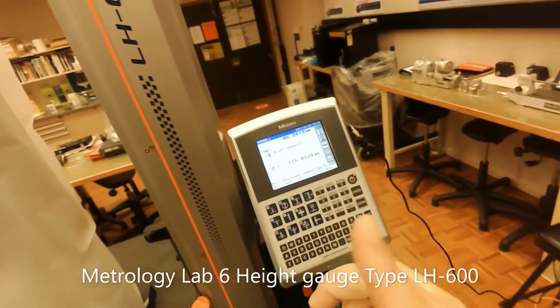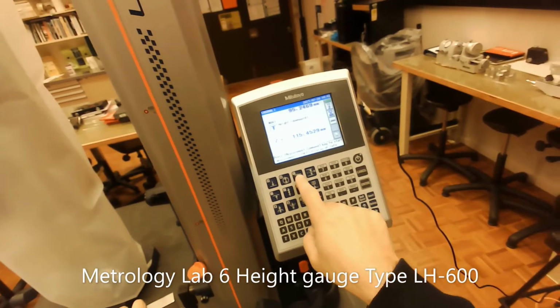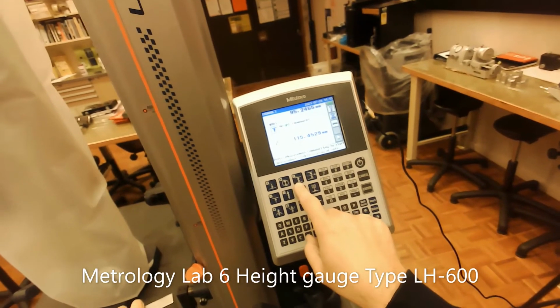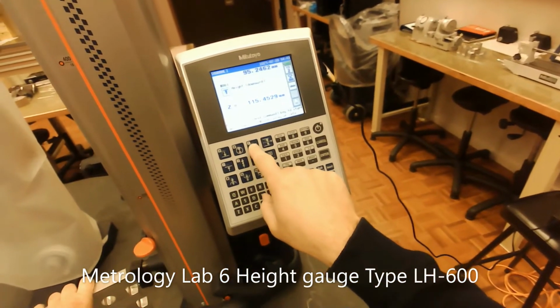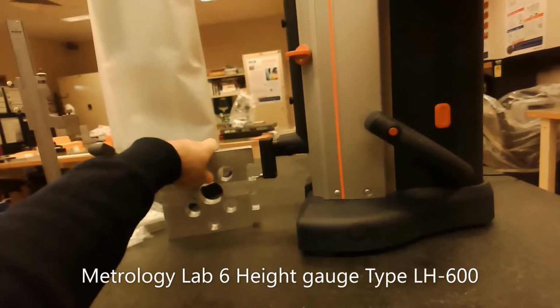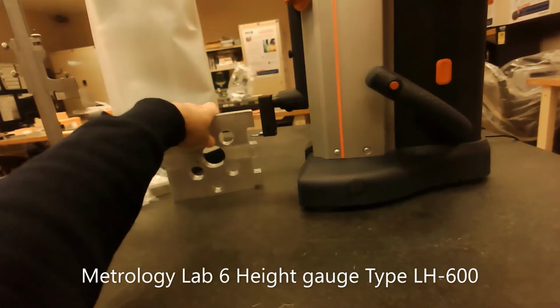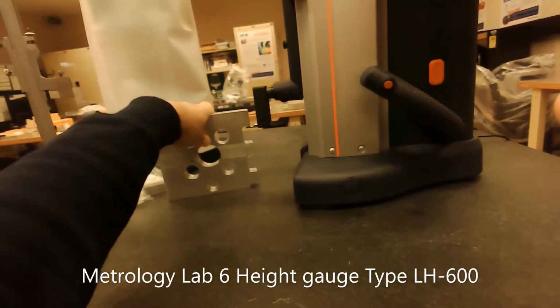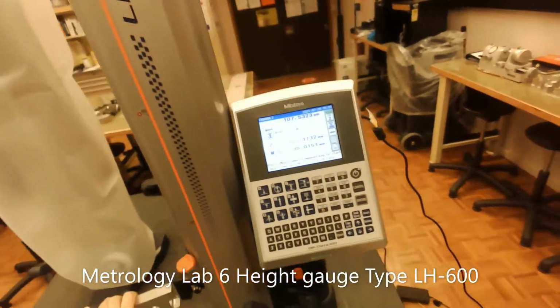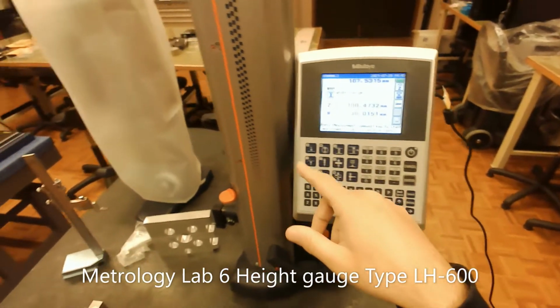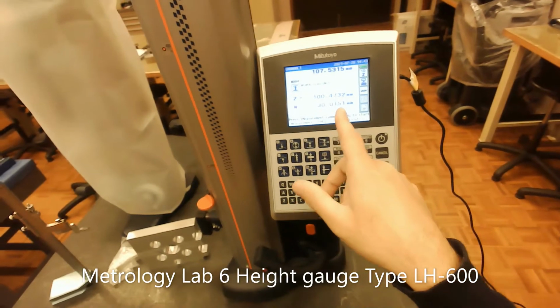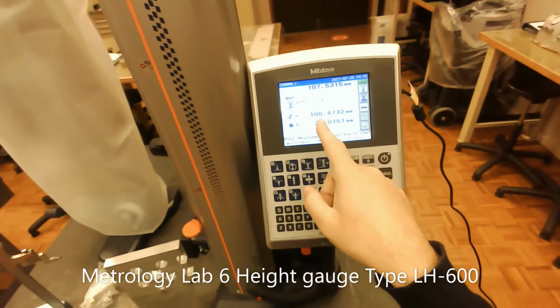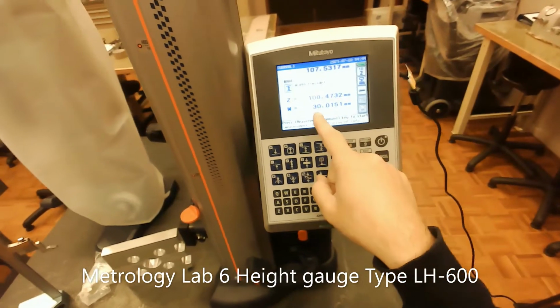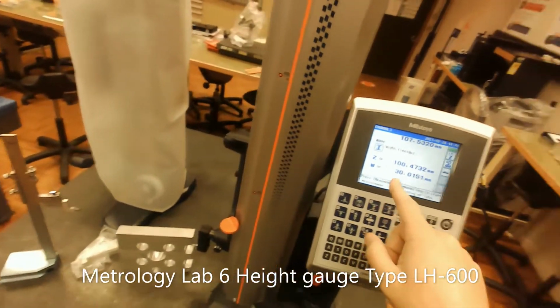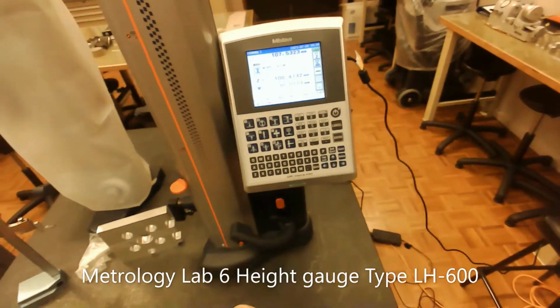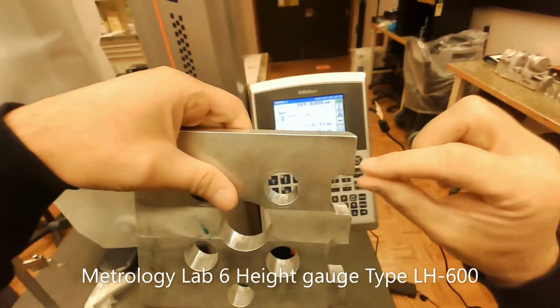To do that, we have a gap. So this is a gap. Two lines, and we need to check what the gap between them will be. Click this option, so it's going down, touches it, and goes up automatically. You can see I didn't touch anything on the device. And it's going to give you the reading. So the height of the upper surface was 100. I think this is for the lower surface, 100, and the gap between the two surfaces is 30.0151 millimeters.